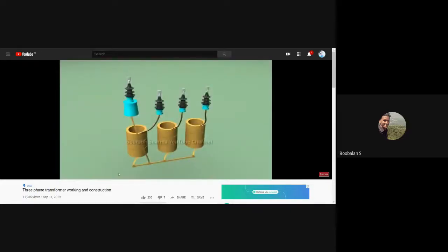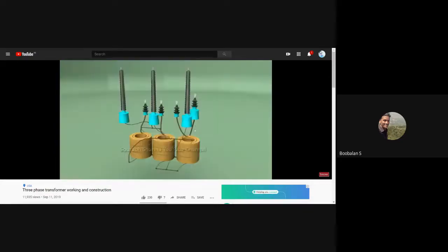In this example, we can see the low voltage winding is connected in star. How can it be done? The lower ends of the three windings are connected to a common point to form a neutral and brought out through this bushing, and the remaining three ends are brought out through these bushings individually to form the line conductors. In this way, the coils are fixed inside the transformer.